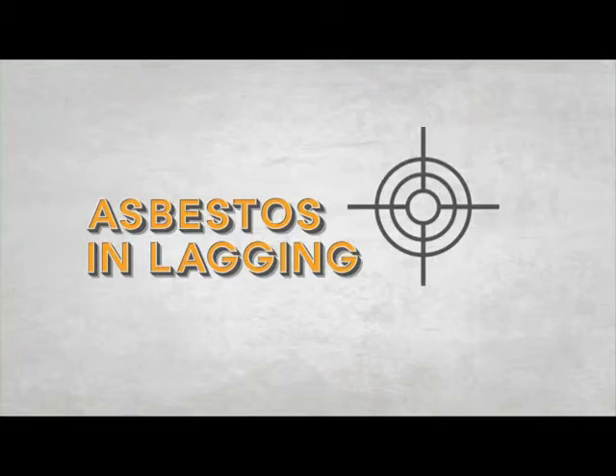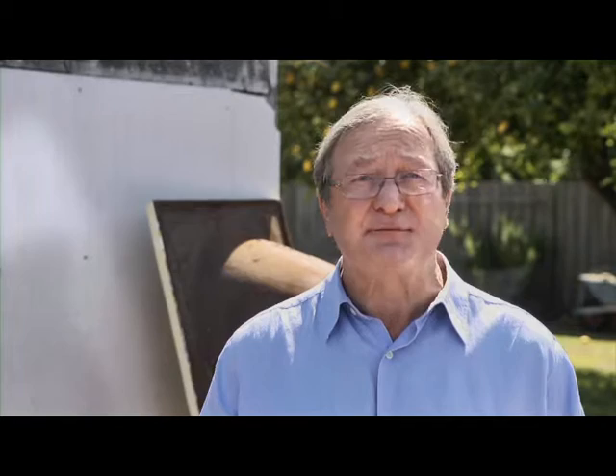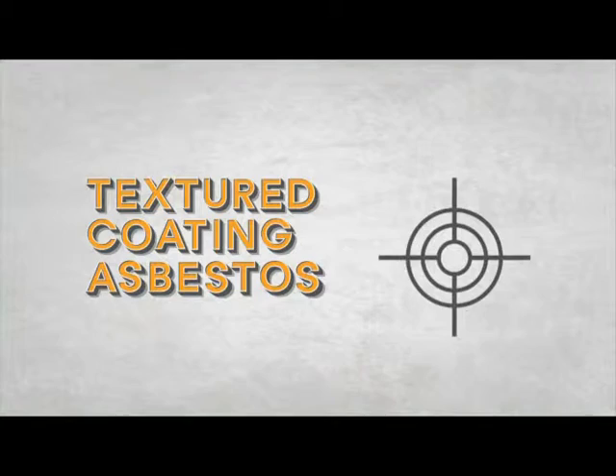Because of its insulating properties, you'll often find asbestos used as lagging around pipes and water heaters — something plumbers should especially look out for. This kind of asbestos can be hard to spot because it's often painted. Electricians need to take special care with electrical switchboard panels and meter panels. Those installed before 1990 will almost certainly have used asbestos as an insulator, and so will many built before 2004.